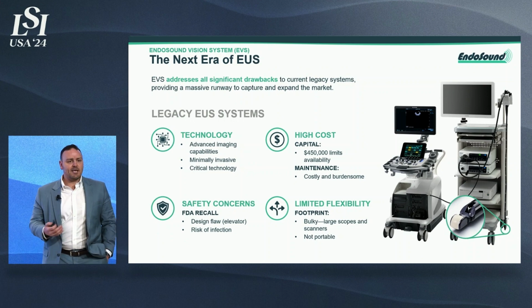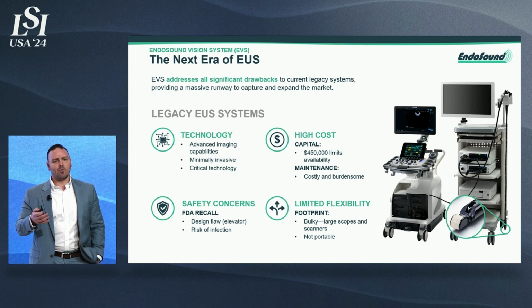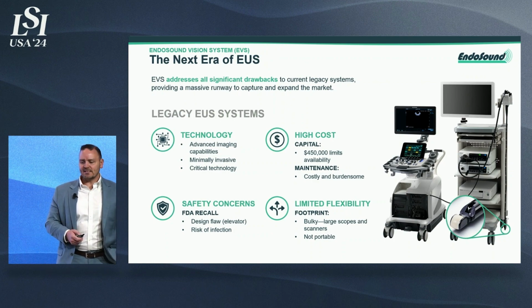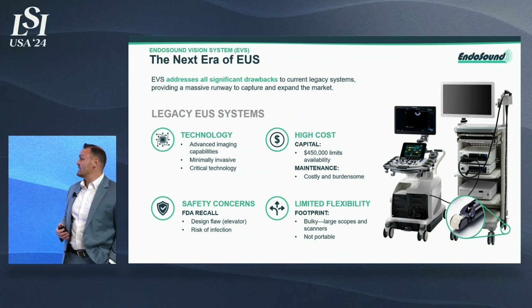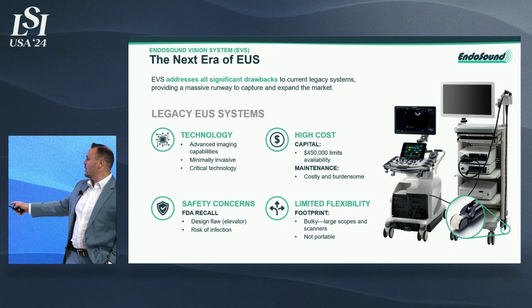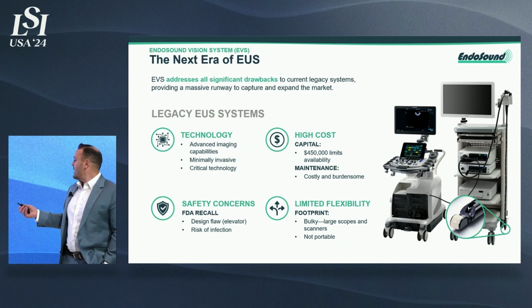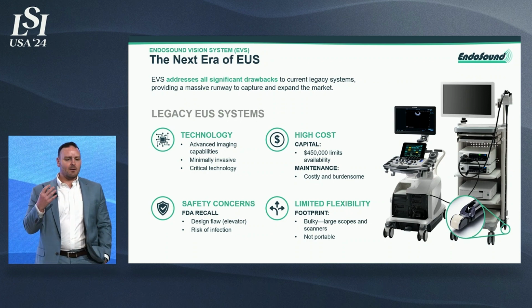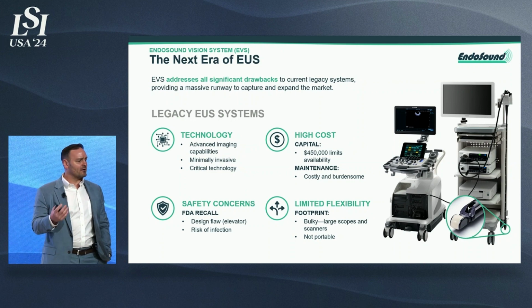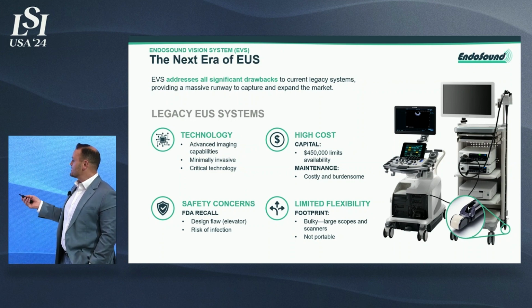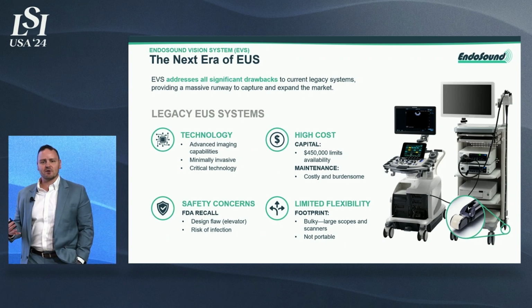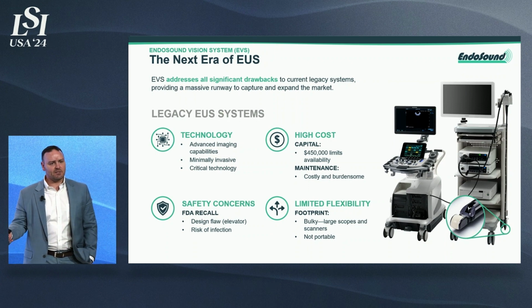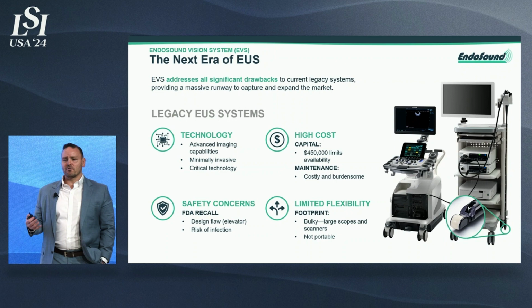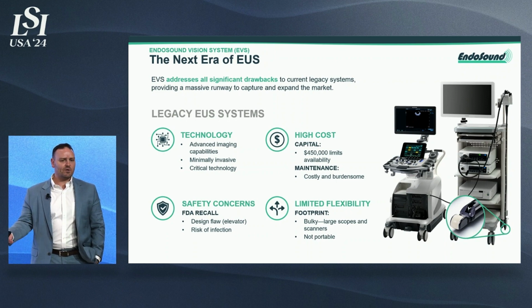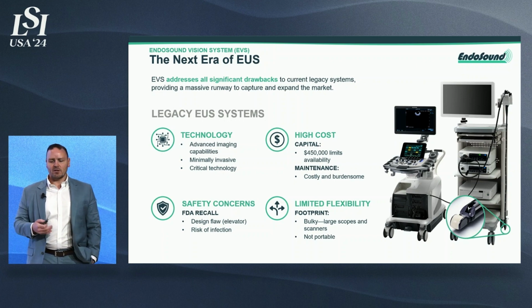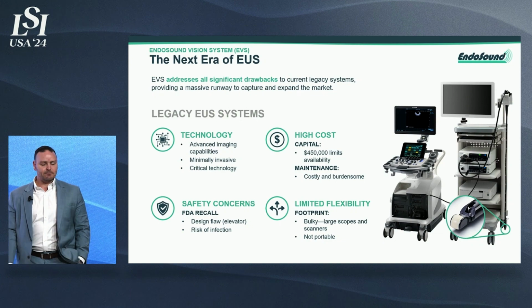Additionally, they're large, bulky systems that can't be transported from room to room or lab to lab or campus to campus. They really reside in one singular room dedicated in the endoscopy suite. And lastly, and probably most importantly, is the design flaw associated with the scopes. If you look in the lower right of the image, you'll see in the channel of the scope a V-shaped steel device that controls the articulation of a therapeutic device or needle during a fine needle aspiration. The problem is there are all sorts of channels and nooks in that area that are very difficult to clean through high-level disinfection or ETO gas sterilization, which is common for these devices. So they can be a harbinger of biological pathogens, which has led to FDA recalls on the ERCP sister scopes and has really been of high note to the FDA and CDC as of late.